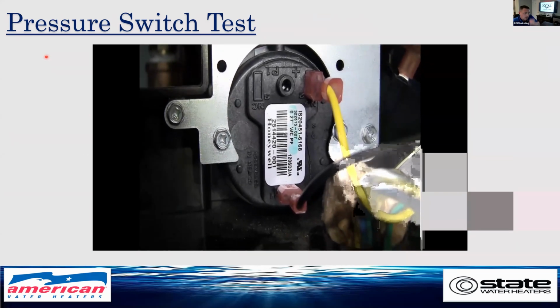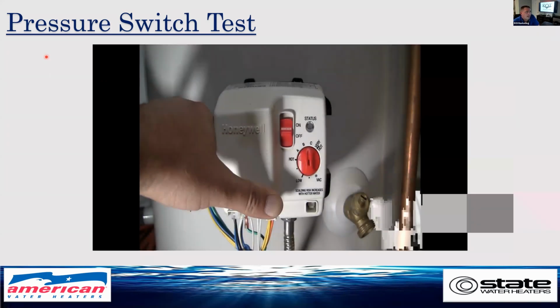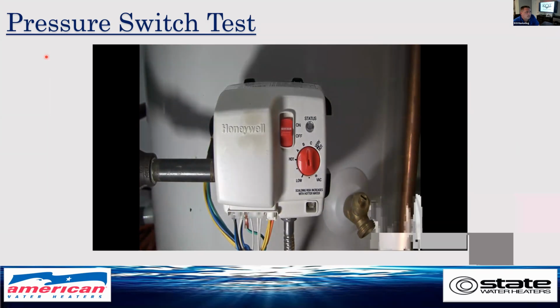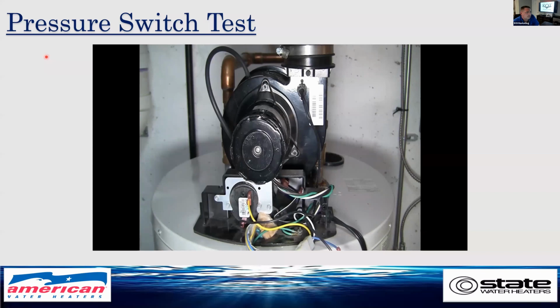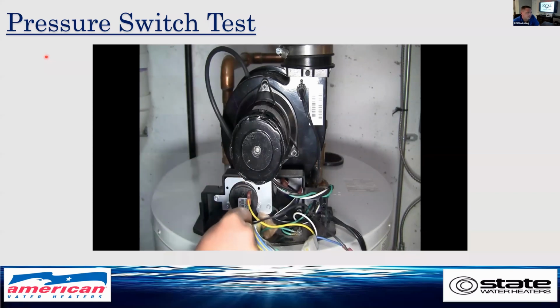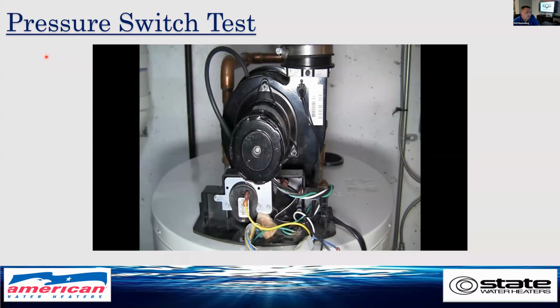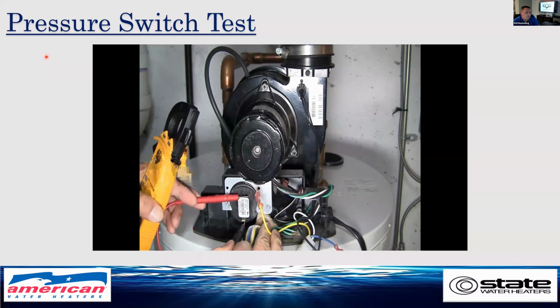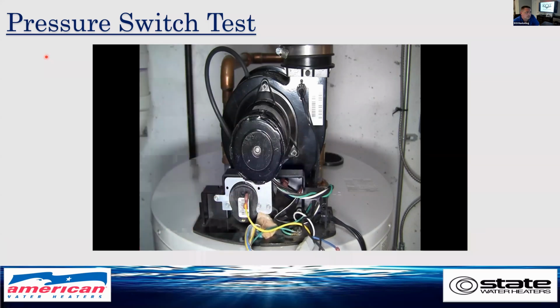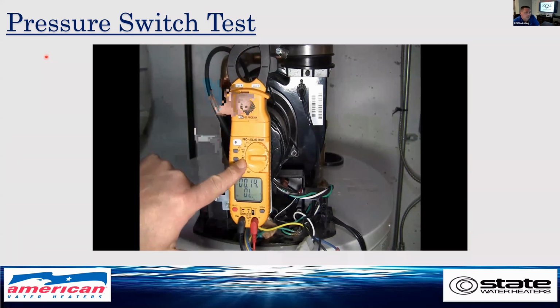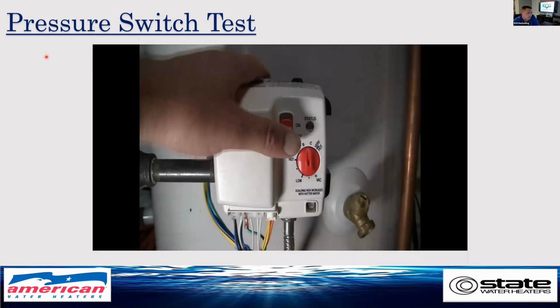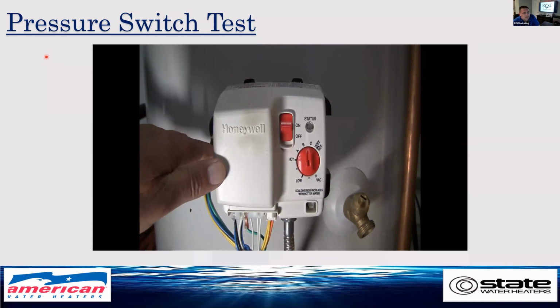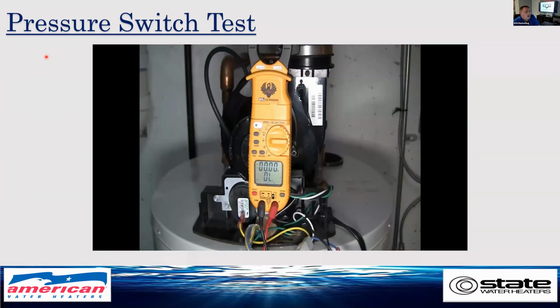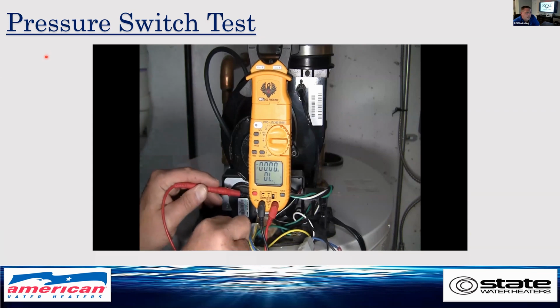Pressure switch testing. I like to test to make sure that it is open before. So I'll cut the gas valve off. Remove my spade connectors from my pressure switch. Make sure I'm set to continuity. Now we'll test to make sure that it closes. Blower turns on, and we should ring out.